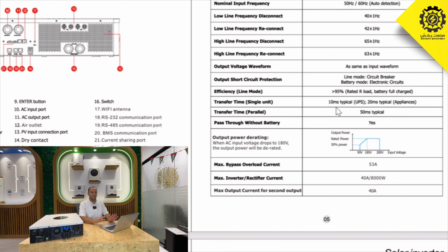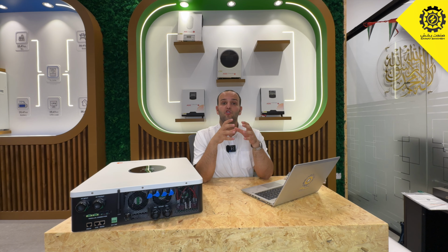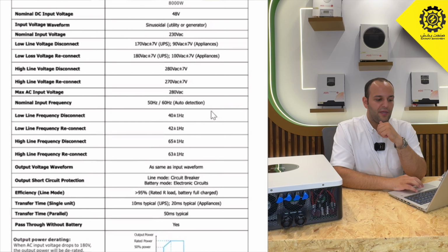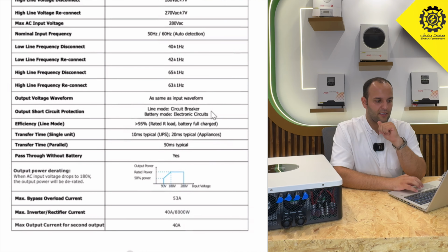Transfer time. Transfer time is so important for whoever wants to use this inverter as a UPS. If you have some rack server or important loads like a router or computer, you must use this inverter, because the transfer time or switch delay time is 10 milliseconds for UPS, and for others like a refrigerator or water pump it is 20 milliseconds. Transfer time in parallel mode is 50 milliseconds.